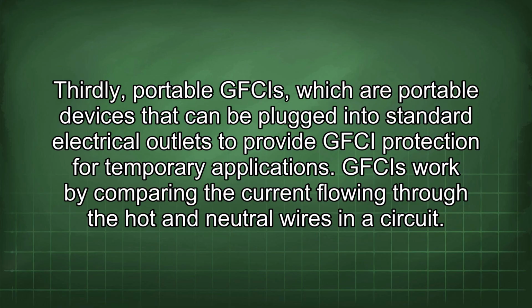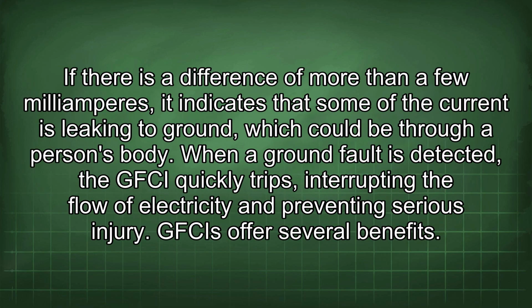GFCIs work by comparing the current flowing through the hot and neutral wires in a circuit. If there is a difference of more than a few milliamperes, it indicates that some of the current is leaking to ground, which could be through a person's body. When a ground fault is detected, the GFCI quickly trips, interrupting the flow of electricity and preventing serious injury.